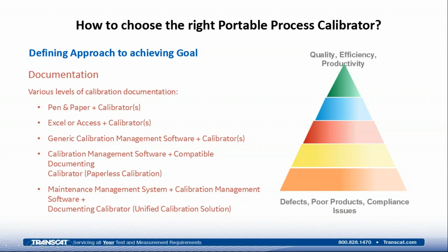Calibration management software plus a compatible documenting calibrator. So this is where we can actually define a process, procedure, routine, and the variables such as tolerance of devices, etc., and be able to download that procedure to a calibrator, perform the calibration, and then upload it back to the software, making it in effect a paperless calibration. And then one step above that is a maintenance management system plus the calibration management software and a documenting calibrator, where this would provide the capability and features to be able to track and trend calibrations, do analytics, preventative maintenance, other capabilities beyond just keeping a record of the calibration being performed.